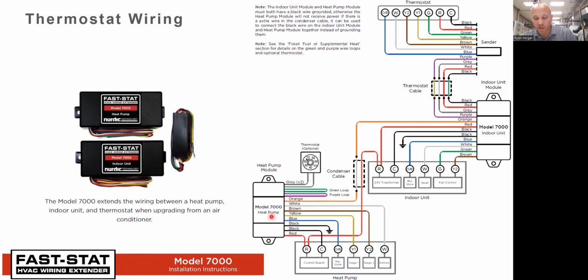So when you're bidding a heat pump upgrade from a non-heat pump system, you may have to do additional electrical wiring, and you may have to do additional electrical low voltage wiring. So that should be included in your cost estimate when you're doing your payback calcs. Don't just say, oh, the heat pump cost whatever, $2,700 more than the AC replacement. Well, it's $2,700 more plus this extra wiring labor. So really maybe it's $3,500 more. You just got to include that math in your payback.